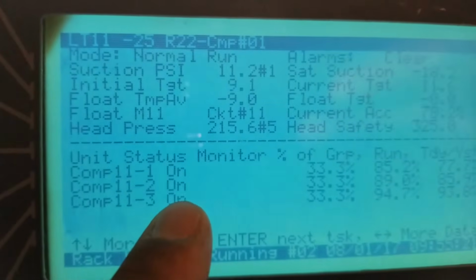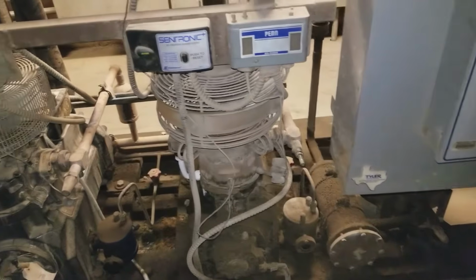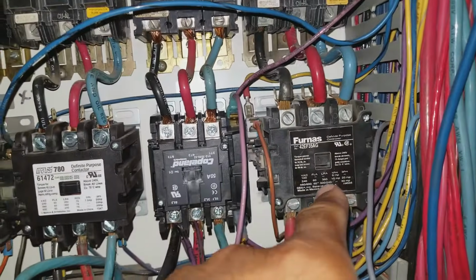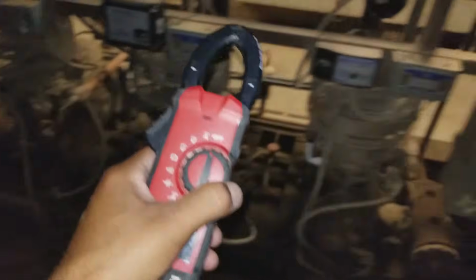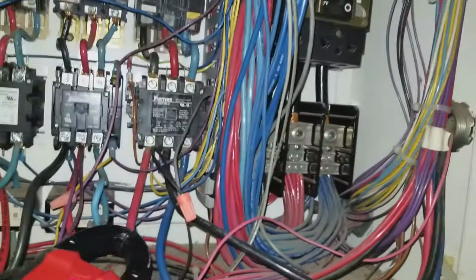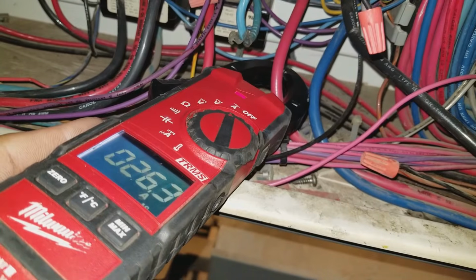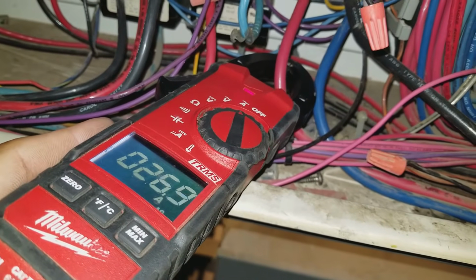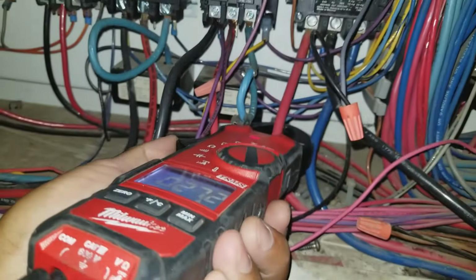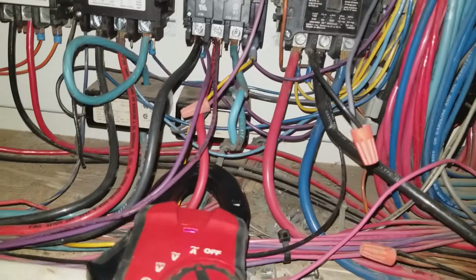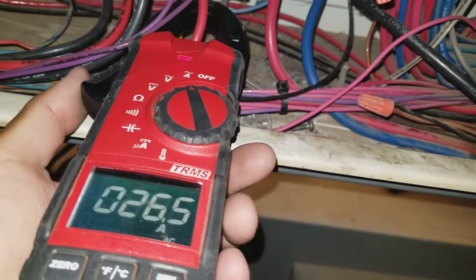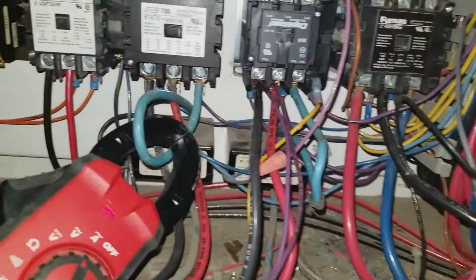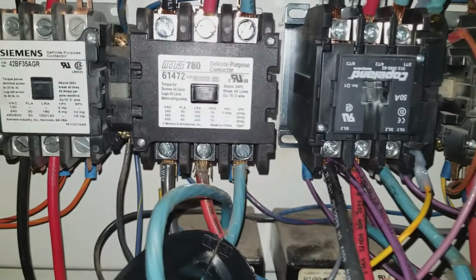All my compressors are calling to be on. Alright, so since all my compressors are calling to be on, go ahead and go. So I got that compressor on. That one's on, that one's on. Let's check it with the amp probe. So that one's running at 26 amps, 27 amps. That one's running. We'll go to my next one. Again, 26 amps. That one's running. This one here, I only have 3 compressors. That one's not running. My contactor's not even pulled in.